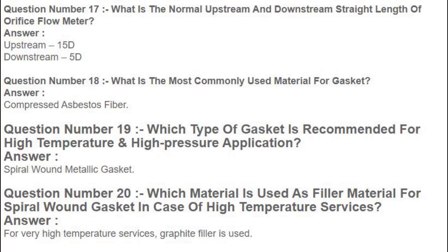Question number 17: What is the normal upstream and downstream straight length of an orifice flow meter? Answer: Upstream — 15D. Downstream — 5D.